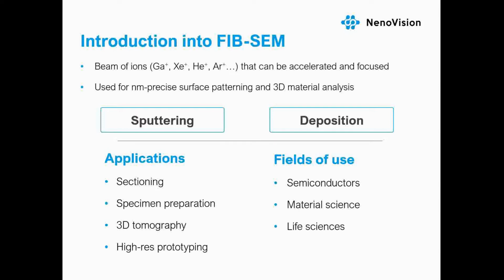Most commercial FIB microscopes are currently equipped with a liquid metal ion source emitting gallium ions because of the robustness and other advantages associated with this technology. However, there are now several alternative ions available via different sources for FIB microscopes, offering a large range of available ion currents, energies, and beam sizes, which is important to various niche applications and higher resolution patterning. The focused ion beam microscopes have been used most significantly in the semiconductor industry, but also in various material and life science applications.